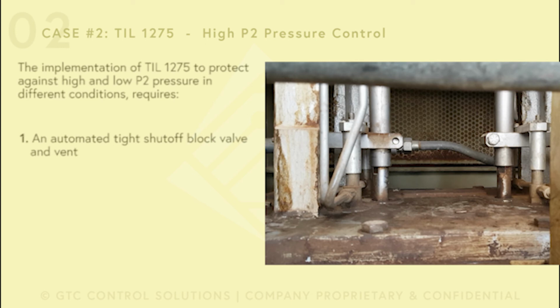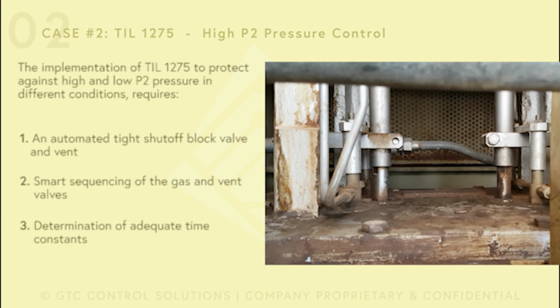It has an ANSI class 4 classification, while the valve upstream of the gas fuel module, which is usually not supplied by the OEM, is customer responsibility. That block valve must be tight shut off, ANSI class 6, and also have a vent to make sure that the space between the block valve and the speed ratio valve is vented, has no gas, and therefore we make sure that the pressure downstream of the speed ratio valve will be less than 6 psi during startup. So you need an automated tight shut off block valve and vent, ANSI class 6 or better, smart sequencing of the gas and vent valves, and determination of adequate time constants.